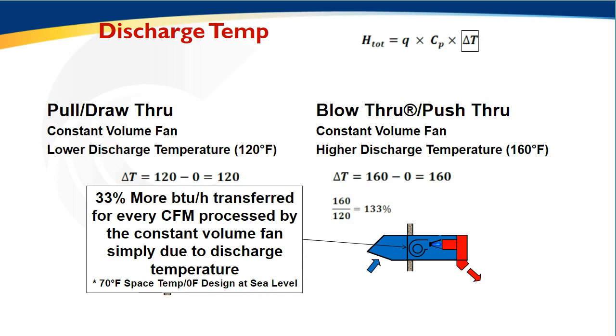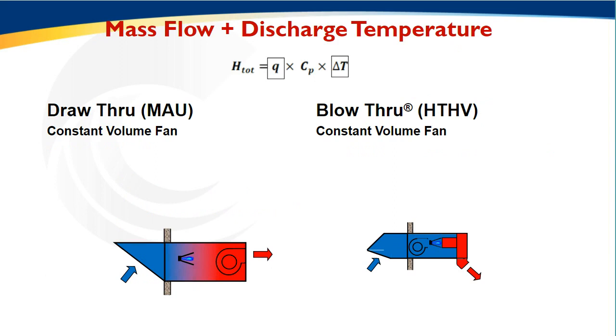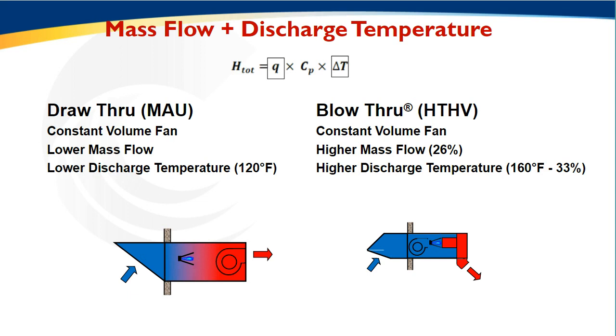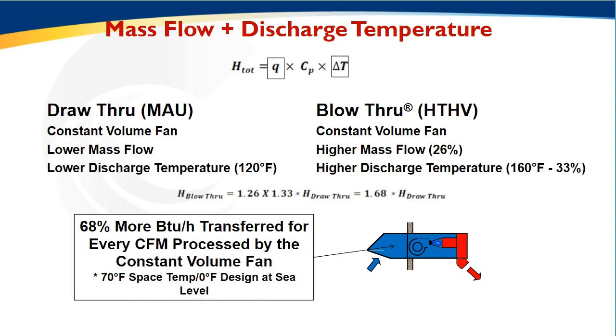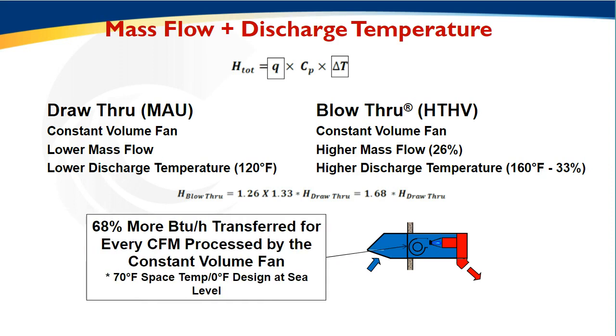And now if I look at those two values, combine those together, this is where HTHV really starts to shine. By allowing for higher mass flow and greater discharge temperature, by combining that 26% and 33% factors, the HTHV technology on a per CFM basis can deliver 68% more energy, 68% more BTUs per CFM. So I can deliver more heat with less airflow.